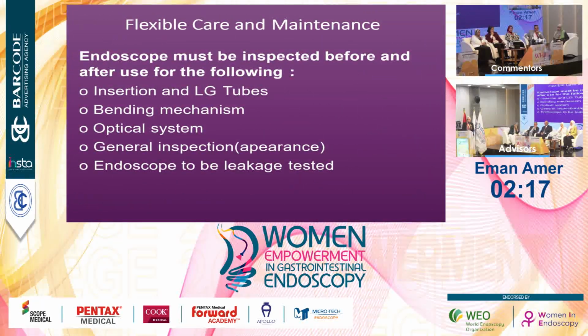Flexible endoscope care and maintenance. It must be inspected before and after use: the insertion tube, LG tubes, bending mechanism, optical mechanism, general inspection for the appearance, and the endoscope is to be leakage tested. And this is very important because you can find a lot of places, if there is any leakage in the scope, to go for the maintenance and to come back for you, it's going to take months and maybe years.